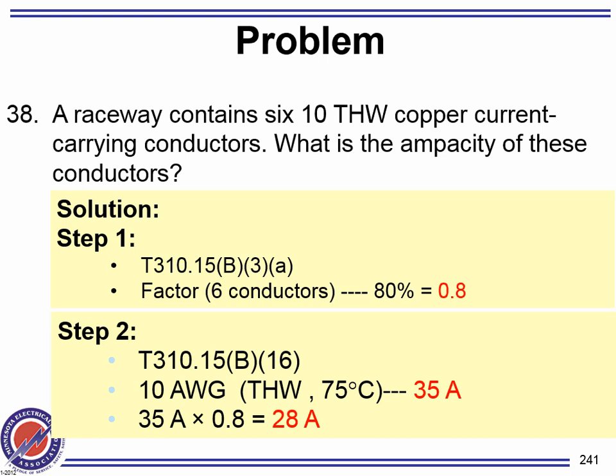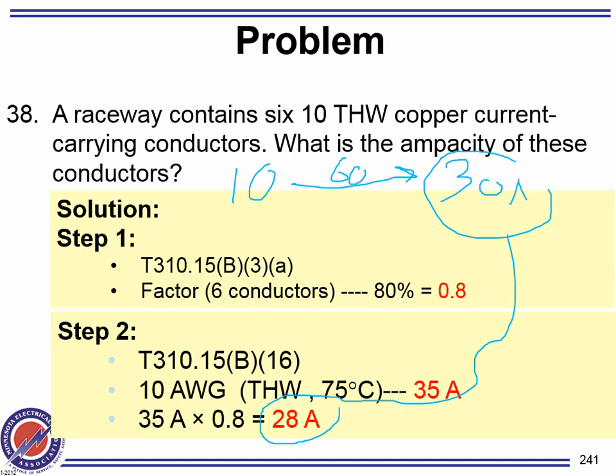Now, here's my question for you. Once you do that, you ask yourself, number 10 under normal operating condition has to be 60. How much current can number 10 carry on the 60-degree column? Is it 30 amps? 30 amps. Now I want you to look at these two numbers and compare them to each other.